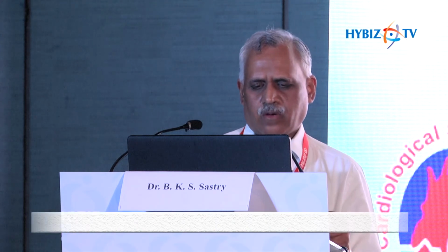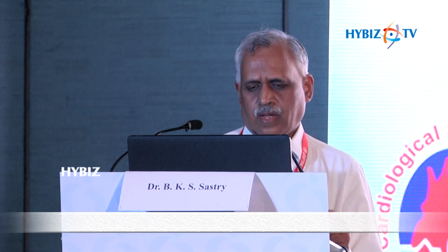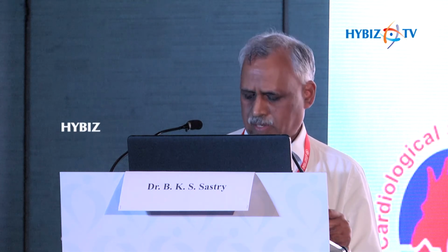Now, the final 2 slides. We know that there are different imported stents, imported in the sense of Xience and all these multinationals, so we are all familiar with these stents. Now look at the platform: they use stainless steel, cobalt chromium, platinum, and the thickness varies from 81 to 112 microns. Except for BioMatrix and Synergy, most of the polymers are durable, non-biodegradable, and of course they use different drugs, zotarolimus, everolimus and sirolimus, we all know that.